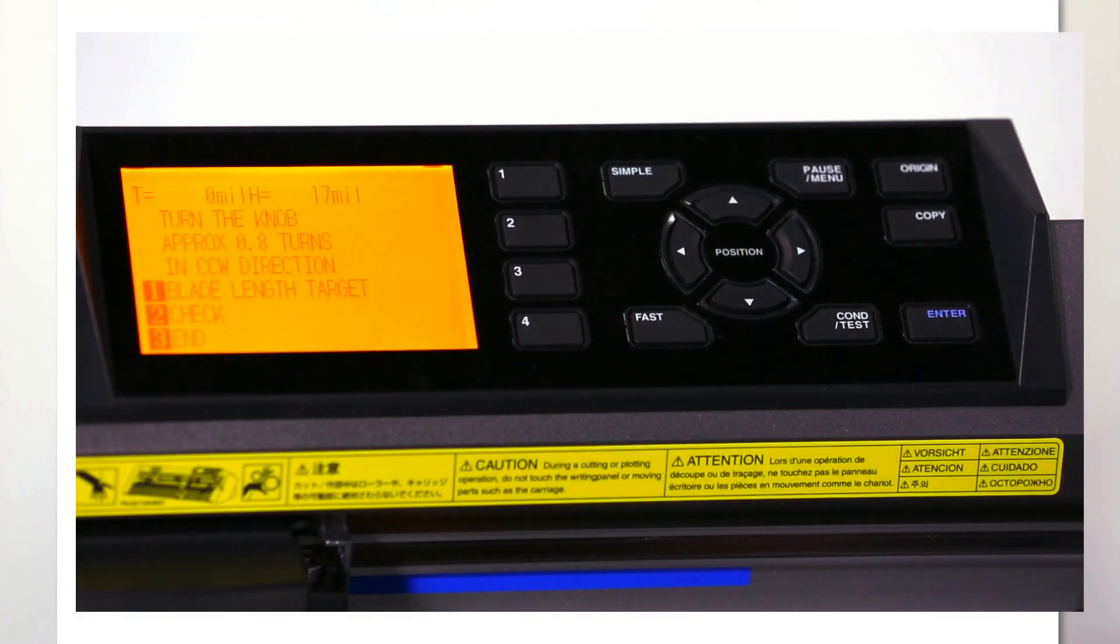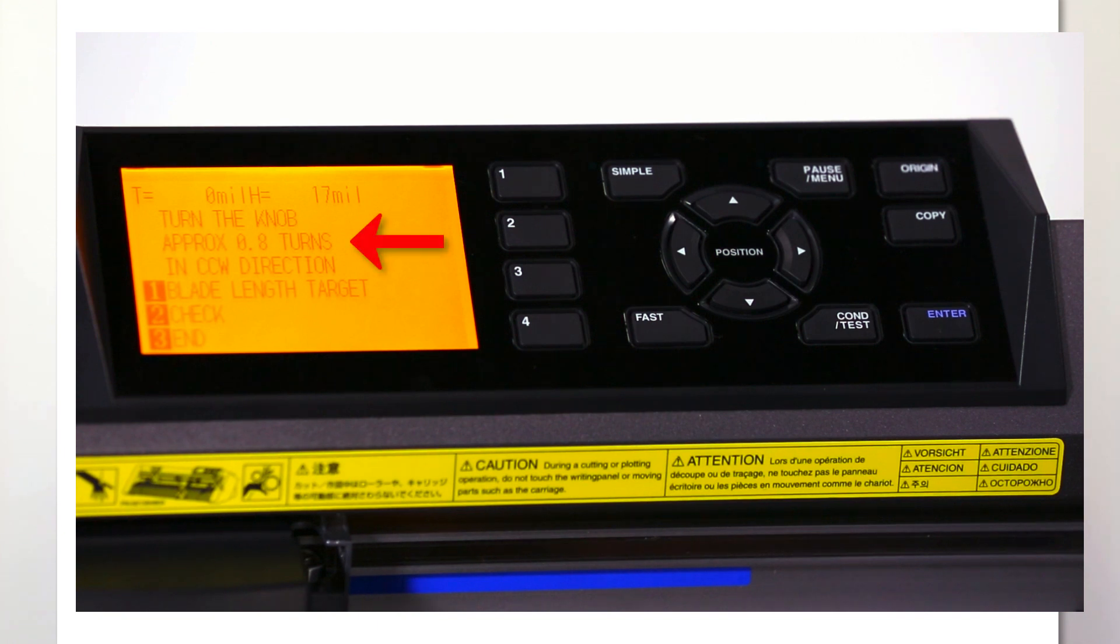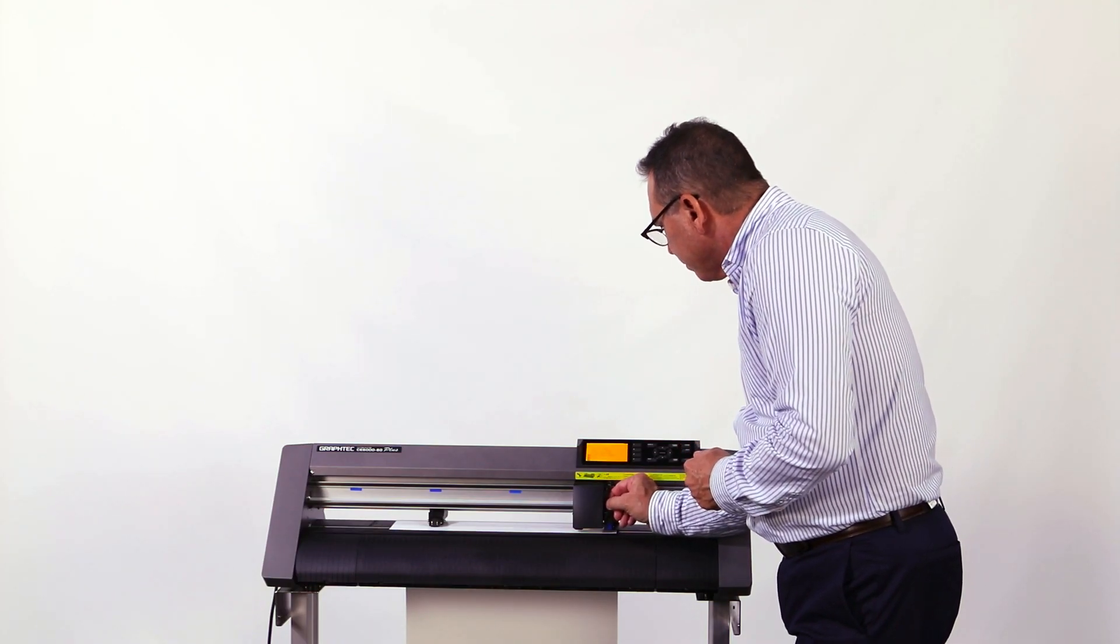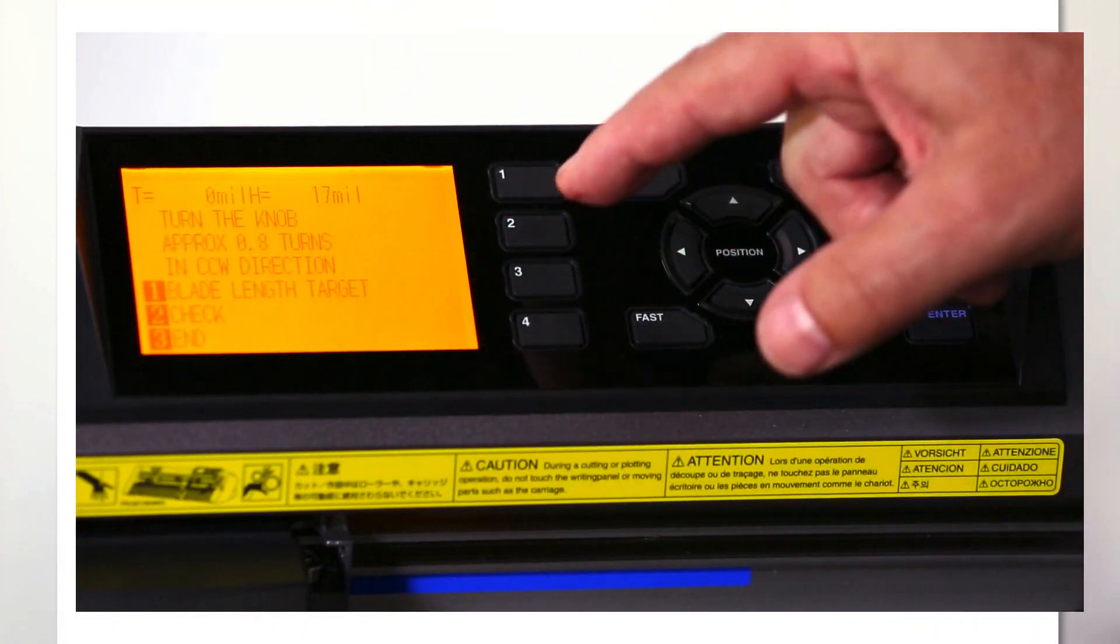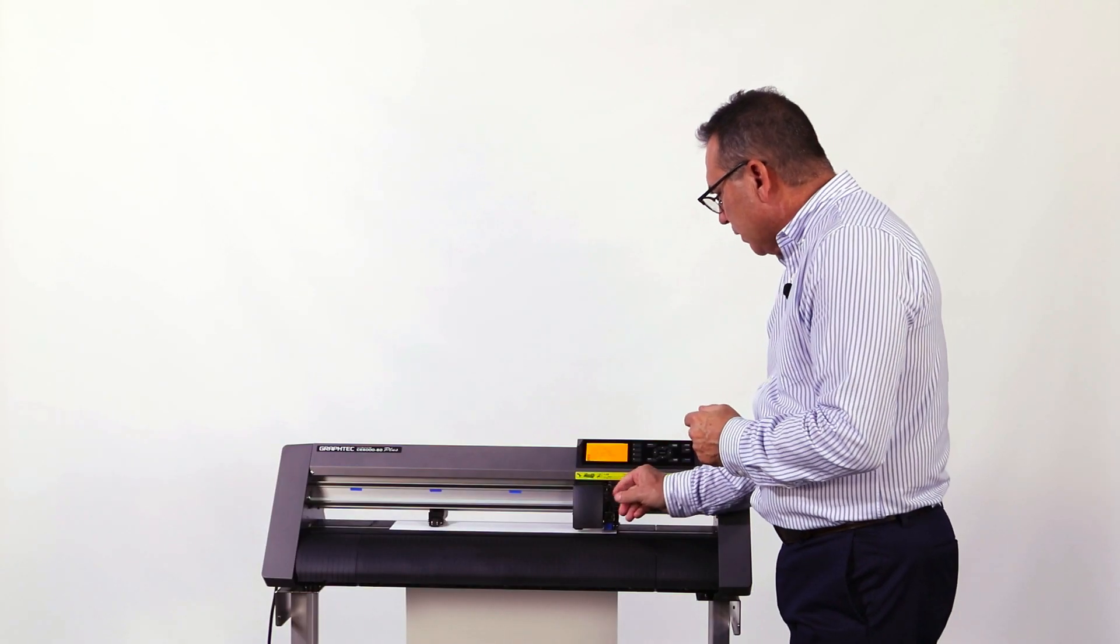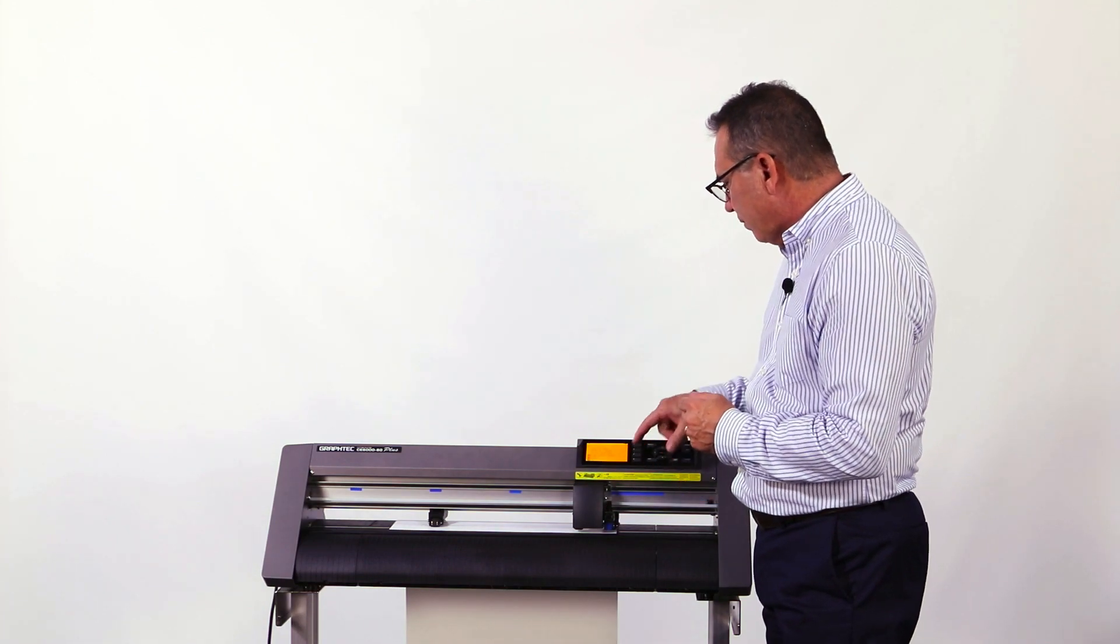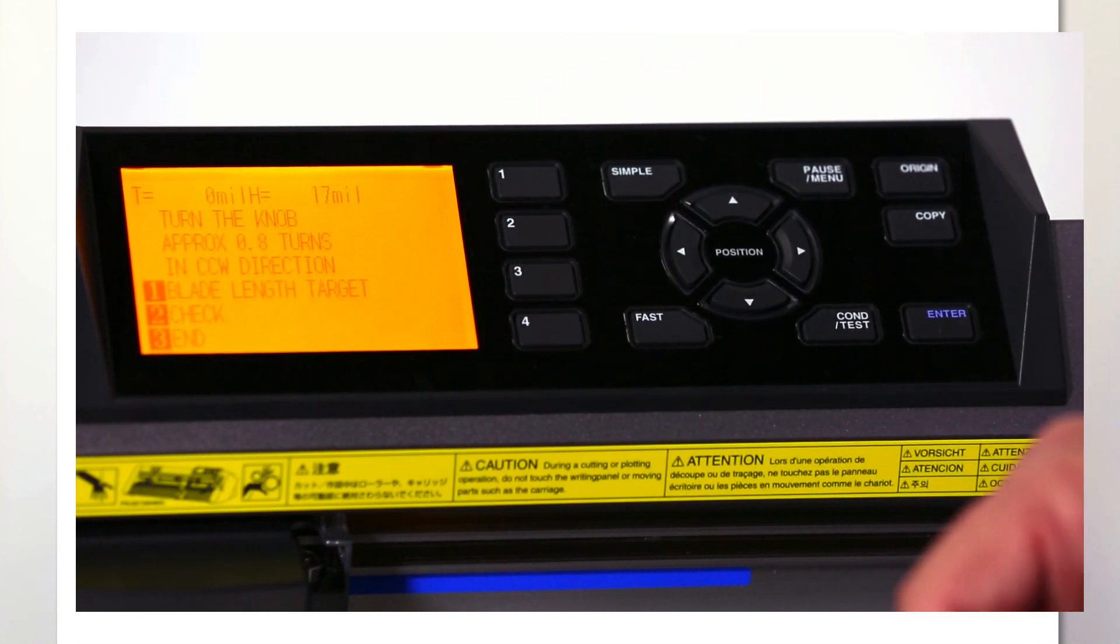Now that the reading says 17 mils, we can also see on the front panel it's asking us to turn the pen holder counterclockwise 0.8 turns. So we're just going to turn a little bit here and hit number two for check. It comes up and says five mils. So we need to turn it a little more. We'll check again, and now it reads 17 mils.